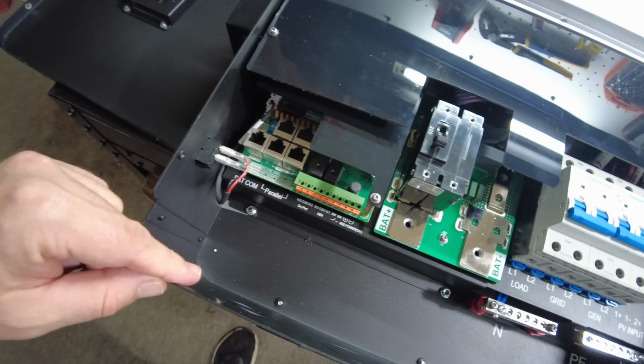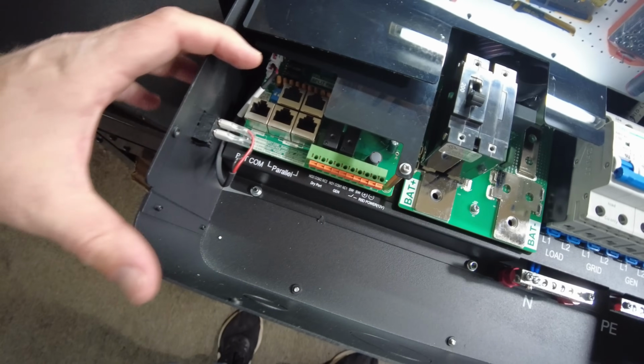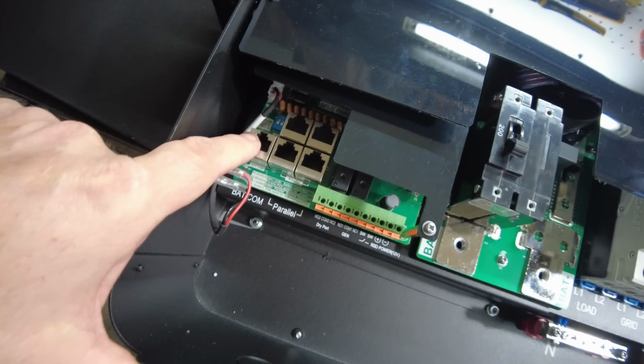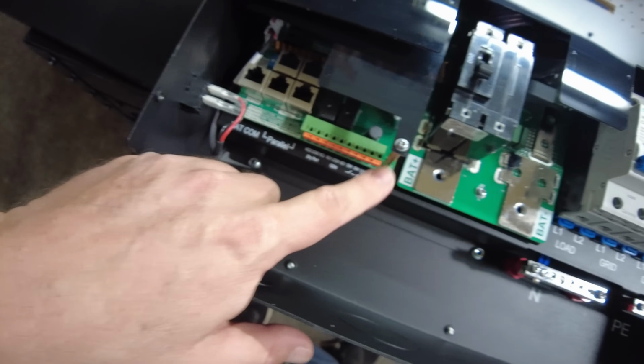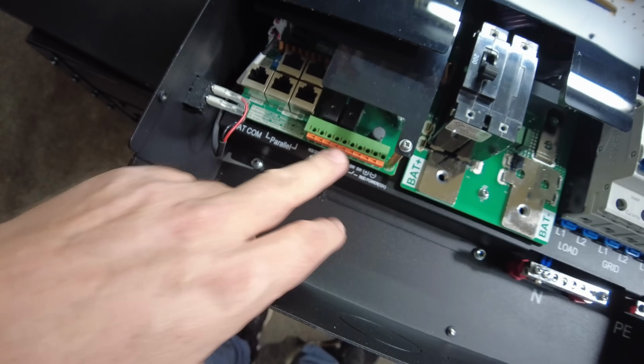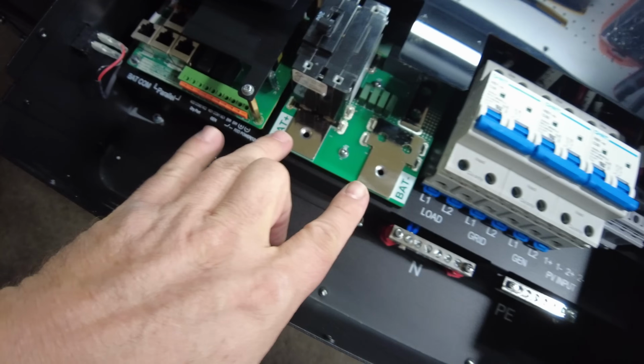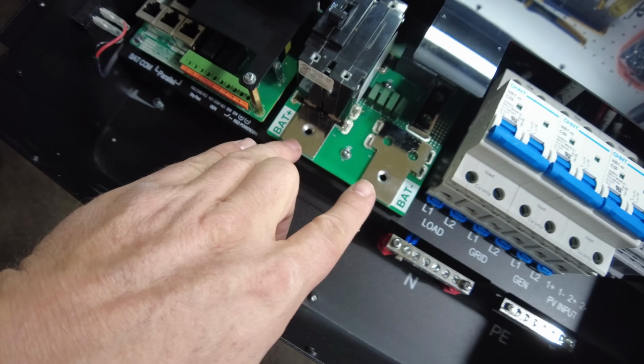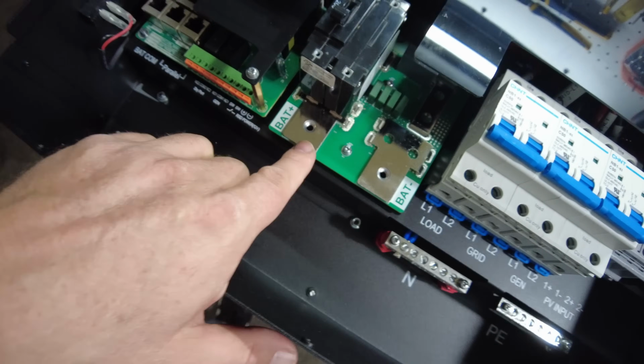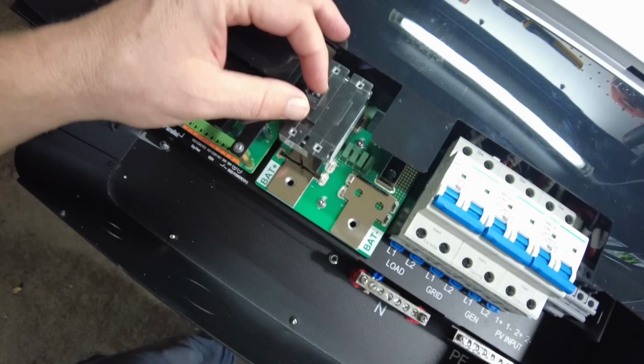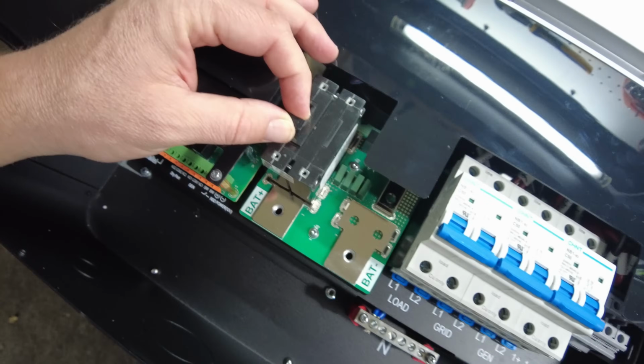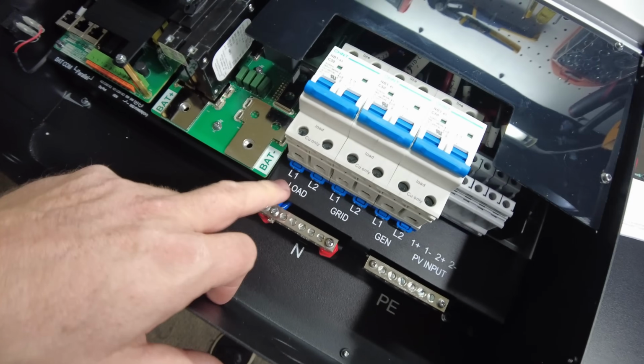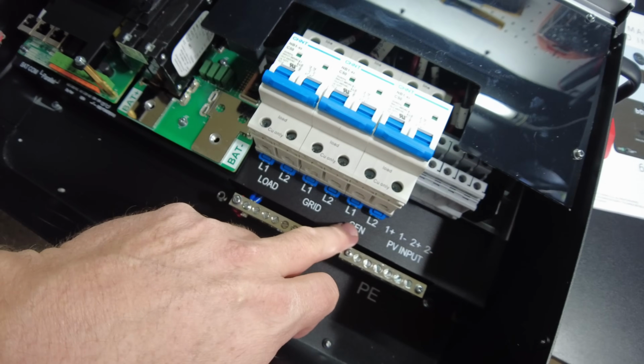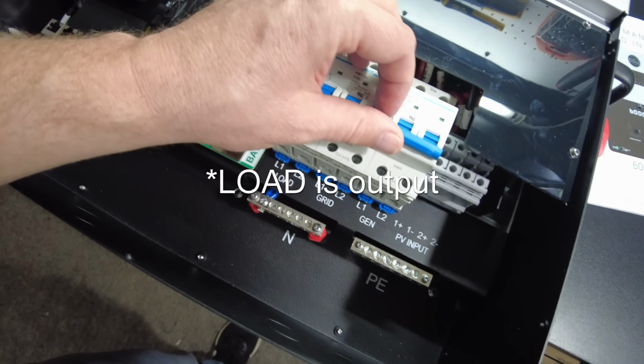All right, guys, let's take a look on the inside here. This looks super clean. Okay, we've got our battery communication section right here. Several different kinds of dry contact options here. That's really awesome. Here's the area where we're going to tie in our battery. So we've got our battery positive, battery negative, and then there's the big breaker switch for that. Then here's our load, grid, and generator inputs with their disconnects.